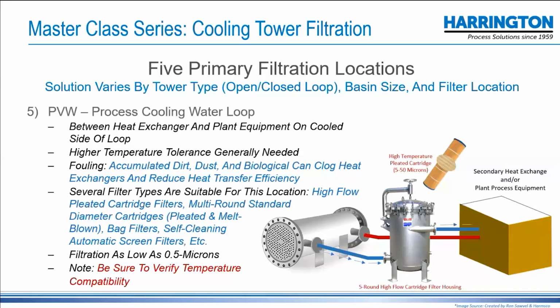So the last of the places where you might effectively filter, other than within the plant itself, where there are a lot of opportunities, is the heat exchanger, from the heat exchanger to the facility. You could have scale solids, you could have byproducts of whatever processes within the plant that you want to get out. You could put it on the hot water side, but you better make sure you've got something that can handle that temperature. In the image you see there, I've got a high flow multi-round cartridge housing that can accommodate high temperature pleated cartridges. Polypropylene typically is good for up to 175 degrees Fahrenheit. You can conceivably see more than that on that hot water loop. So just something to take into consideration.